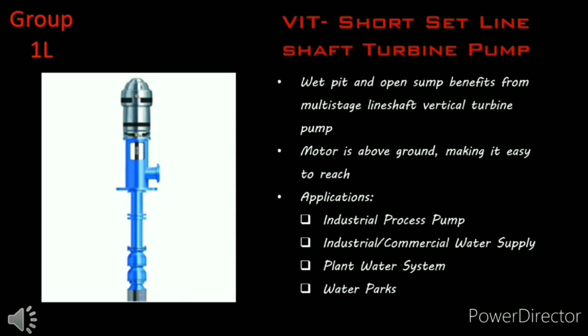Depending on the application, line shaft column assemblies can be open or enclosed. There are several applications for this type of vertical turbine pump, which are industrial process pumps, industrial or commercial water supply, filter backwash, plant water systems, water parks, as well as dewatering and flood control.